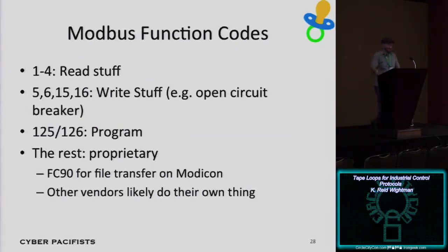So these are what the Modbus function codes mean. Like I said, there's this 1-byte function code field. 1 through 4 are defined as different read commands, whether you're reading an analog value or a discrete value. The actual address that you're reading is all defined by the vendor of the controller. Function codes 5, 6, 15, and 16 are write commands. That's how you issue an operator command to the real world: open a circuit breaker, open a valve, close something, whatever. There are two function codes defined by the Modbus standard for programming the PLC, for actually uploading new ladder logic to the PLC. I don't see that typically implemented by vendors. The one vendor I've looked at that implements ladder logic upload over Modbus is actually Schneider.